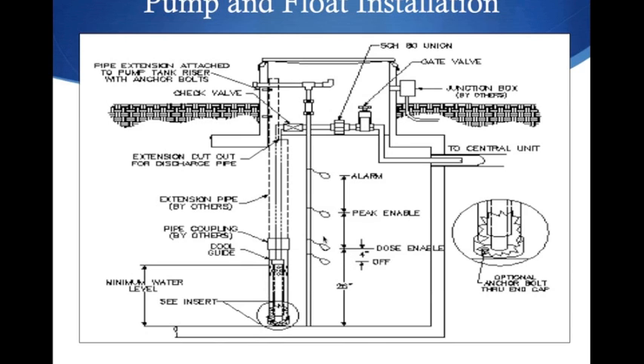Under normal operation the dose enable and off-float are both up and the system is designed to get rid of approximately sixty percent of the flow. If the water level continues to rise hitting the peak float, we'll automatically decrease the rest period, taking the system up to one hundred percent of the design capacity. If the water level continues to rise, we'll hit the high water alarm and turn on that red light and buzzer.